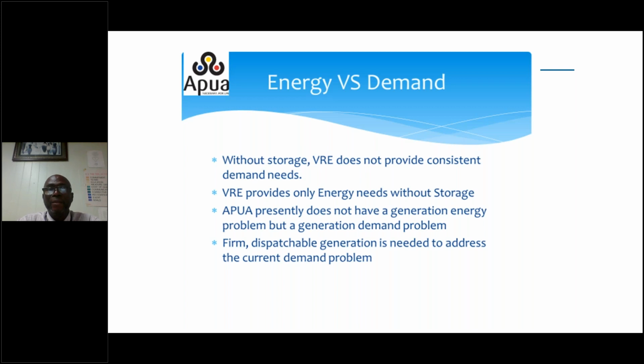Energy versus demand. In Antigua, we don't have a major issue with energy, having enough generation to supply the energy needs of the country. What we have, as I just mentioned, is a demand issue, where, in fact, just recently, we had to be shedding load because two of the major sets were off on maintenance. So you need that reserve capacity to prevent the utility from shedding load. When we look at the last couple of years, the gen sets at the power plants have distributed much less energy than the capacity of the plant, somewhere in the region of 50%, 60%. So it means that there's a lot of energy that can be distributed at the plant, but what we have is a demand issue. Next slide, please.